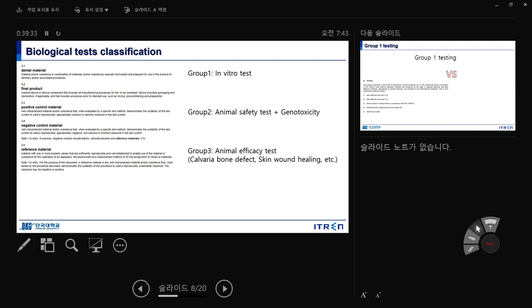In our case we already check bio-efficacy. Group 2 is animal safety testing using animals, except genotoxicity where we use bacteria or virus. Group 3 is animal efficacy testing — when you do calvaria bone defects, skin wound healing, or knee joint replacement, this is categorized as Group 3 efficacy testing. Always remember this terminology, as people often misuse or misunderstand it.